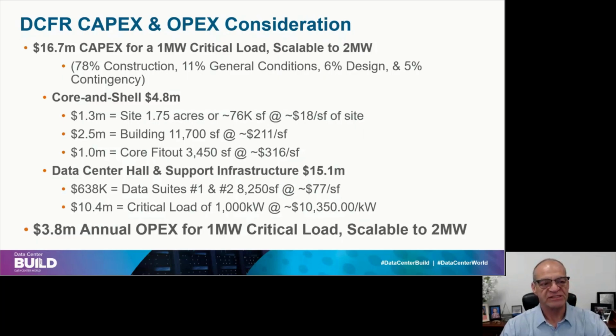So I know everybody wants to see this slide, the CapEx and OpEx considerations. And so here's what you're looking at. That building cost about $16.7 million from a CapEx for a 1 megawatt build. It is scalable to 2. And your breakdown: 78% is in construction, 11% general conditions, 6% design, 5% contingency is built into that. And core and shell of that was 4.8 million. I'm not going to read them, but you could see the costs per building and the cost per square foot, the cost for the fit out. But the real slug right there, the data center hall and support infrastructure, $15 million build, right?